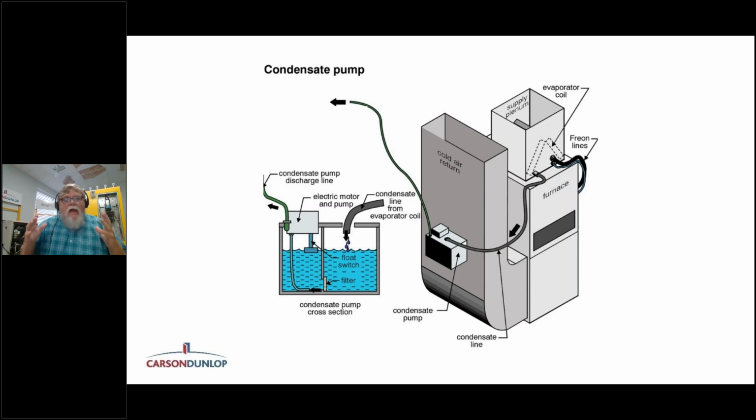And so I used to always tell guys when I would do these classes, if you see these wires hanging out of the unit, report that they didn't use this switch. It comes with the equipment. They give it to you and people wouldn't use them. The HVAC guys wouldn't use them. So I say, absolutely, use them. Now it's actually noted in some of the codes where if the unit's in the attic, you have to have a condensate pump up there for some reason, or if it's in a crawl space or something, you're supposed to make sure that it shuts the equipment down.